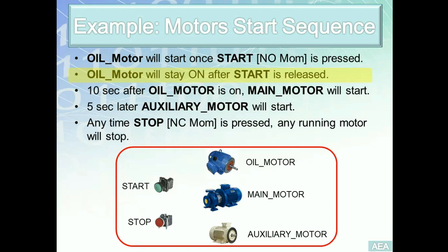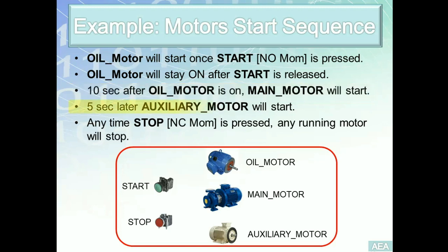Requirement number three: ten seconds after oil motor is on, main motor has to start. In other words, the only condition that will trigger the main motor to start is a time delay of a value of ten seconds. Requirement number four is a similar requirement. It's a five second timer delay that's going to trigger or start the auxiliary motor.